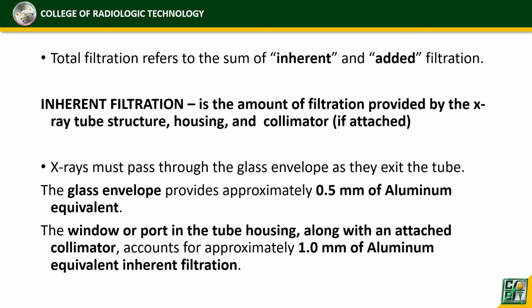In the housing, we have the glass envelope, right? We have the glass envelope, which is made of Pyrex. This glass envelope provides approximately 0.5 millimeter of aluminum equivalent filtration.